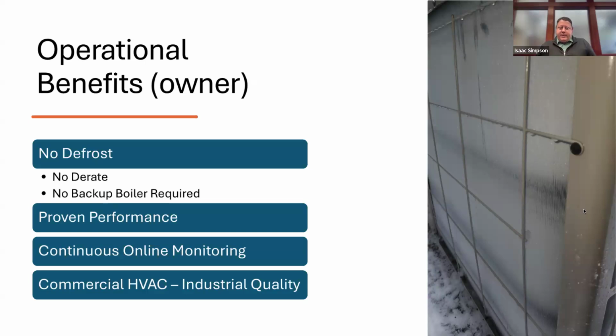So one of the biggest benefits of a Flow system is that by never going into defrost, by not having that reversing valve inside this heat pump system, you're not going into defrost mode and spending that extra energy. So right there, that's a big win. You're also not, depending on where the heat pump is located, de-icing the coil and putting a lot of water onto, say, a sidewalk that then gets icy. So right away, defrost is a big one.